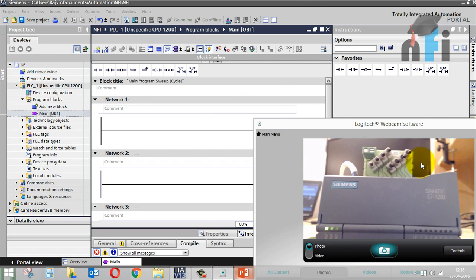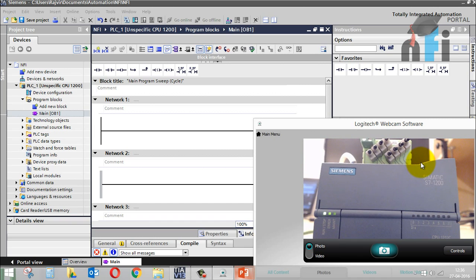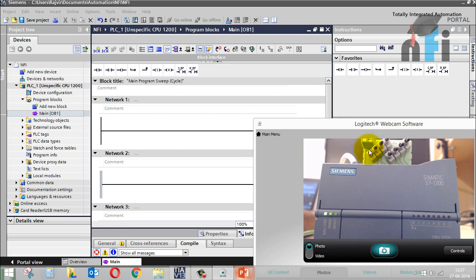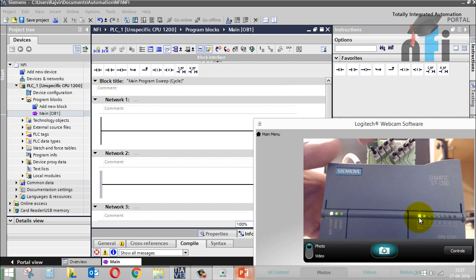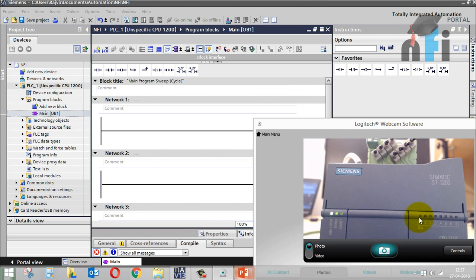We have this simulator — this is called a PLC simulator. Now if you see this, this is the first switch, a physical switch — this is a toggle switch. If I make it on, this will be true. So if I turn it on, this first input is true. Inside the processor, there is a contact — we call it the NO contact. When this NO contact is tagged with the address of this input, that contact goes true. This is my switch, and inside it's a contact. So don't get confused — we have switches and contacts separately, and their functions are different.